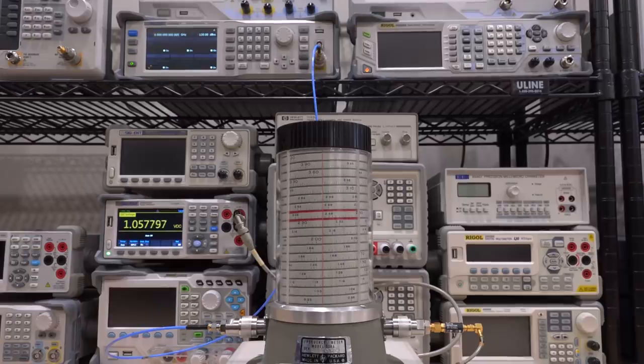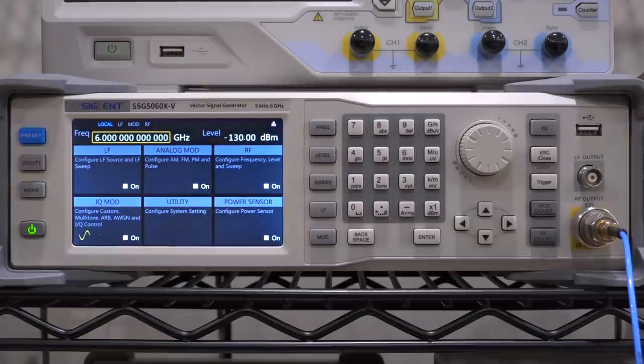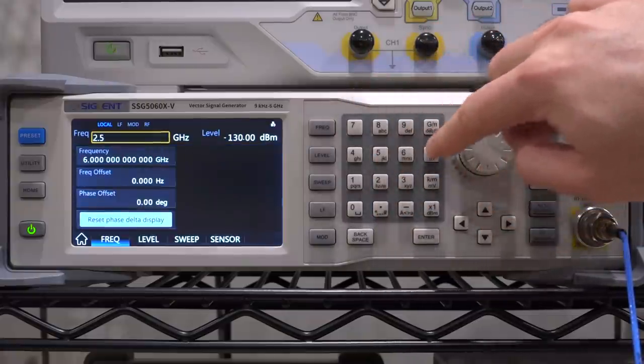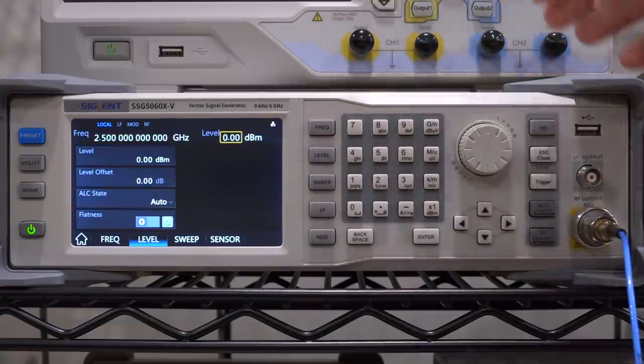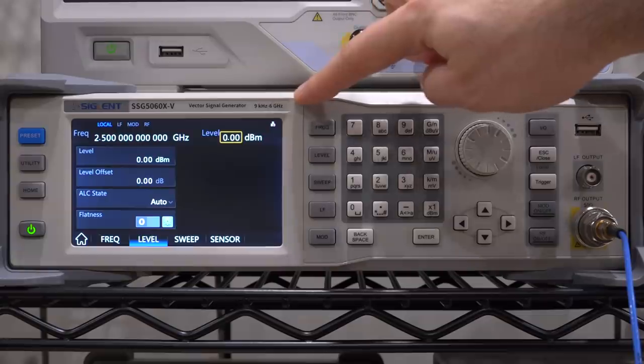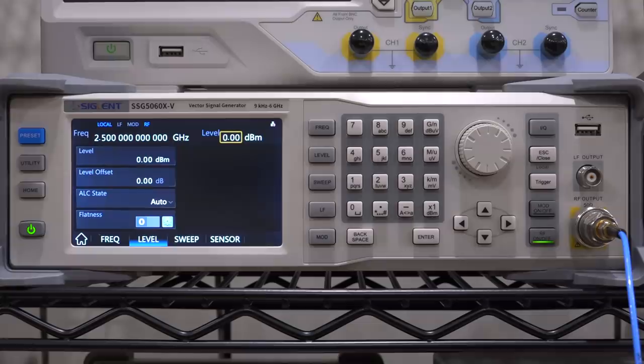So let's go then take a look at the settings on the RF generator so we can see what kind of numbers come out. So here's the Siglent vector signal generator let's set it up to some basic settings let's try two and a half gigahertz here. Now one of the things to keep in mind is that this particular model has the OCXO option the oven controlled crystal oscillator meaning that it produces very very accurate output frequency so two and a half gigahertz is indeed almost exactly what we're going to get out. Let's set the level to zero dBm over here okay so that's it pretty straightforward. Now we're not using the vector modulation capabilities of this yet which means that this is going to generate only a single tone output at exactly two and a half gigahertz. We can go ahead and turn it on there we go basic setting let's go back to the measurement.